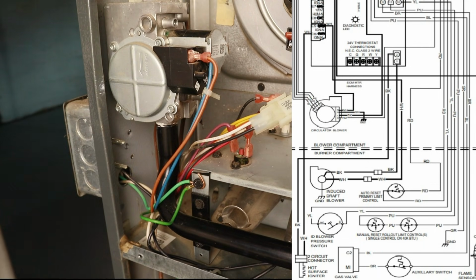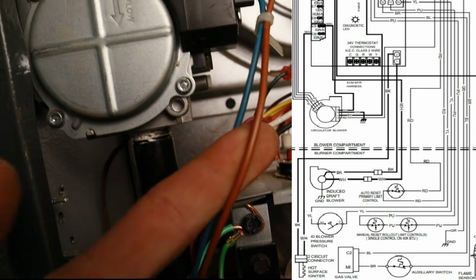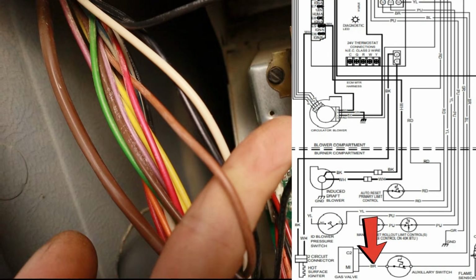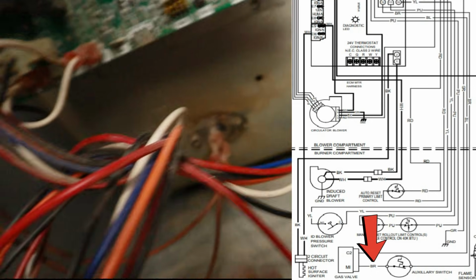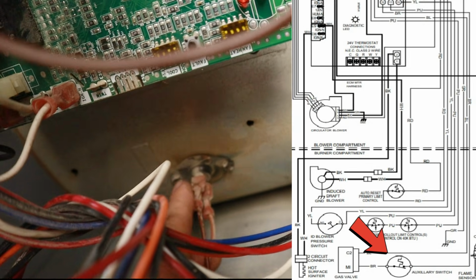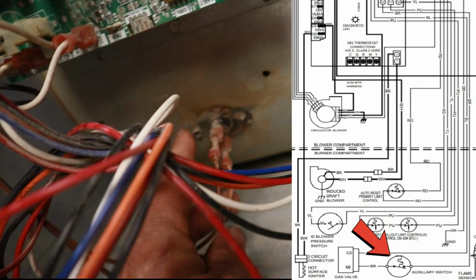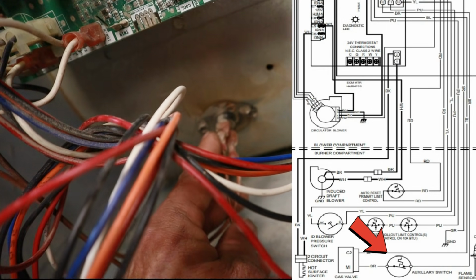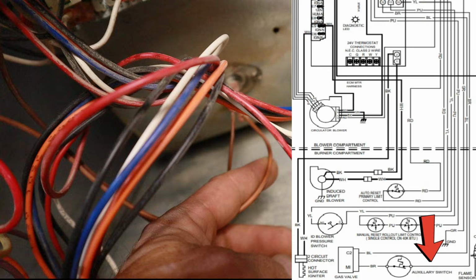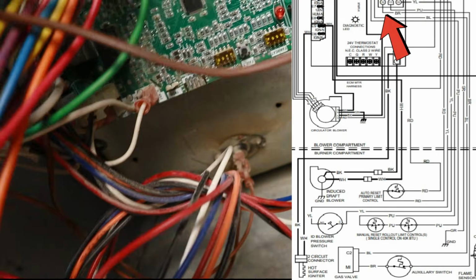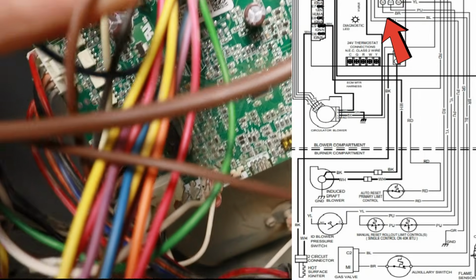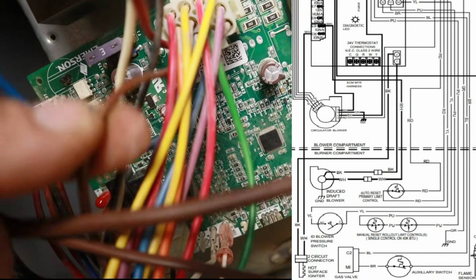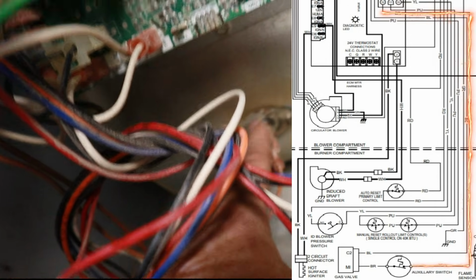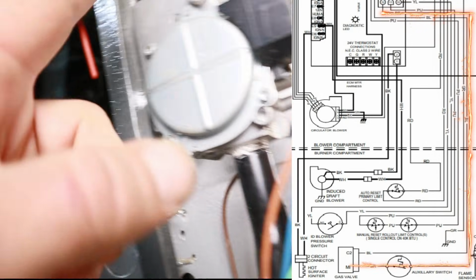Now on the schematic, when we look back, we see an auxiliary switch, which is another temperature limit switch. Now when we trace this brown wire back, it goes down through here, comes down through here, here's our brown wire here. All right, and it keeps going, and we can see that it goes to another temperature limit switch that's located right on our blower casing. All right, so this is sensing whether or not the blower itself is overheating. Then we have another brown wire coming out of that, and that will bring us back to our Molex plug here on the unit, the control board. So this is basically our control board sending 24 volts out to this thermal limit on our blower, which is then going up to the gas valve.